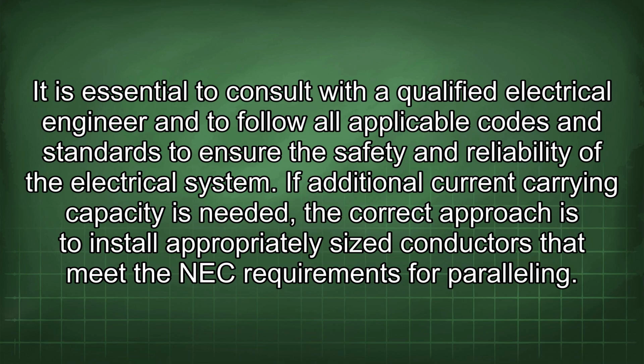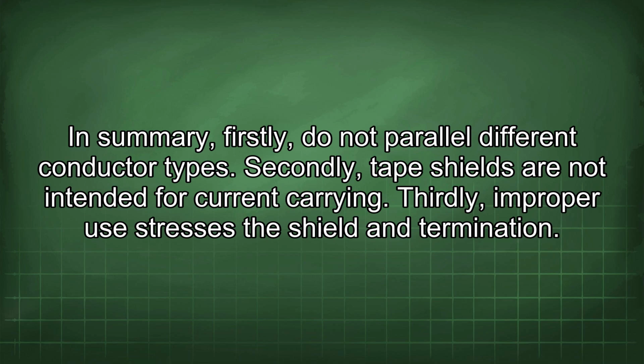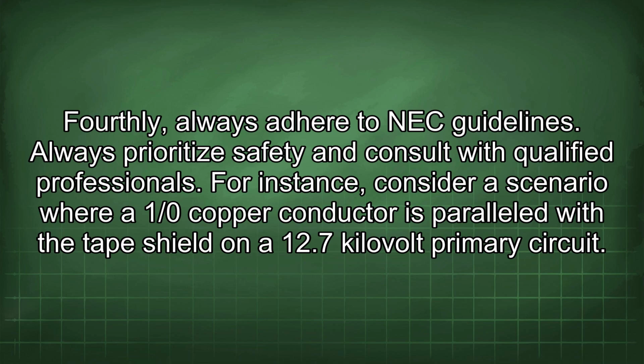If additional current carrying capacity is needed, the correct approach is to install appropriately sized conductors that meet the NEC requirements for paralleling. In summary, firstly, do not parallel different conductor types. Secondly, tape shields are not intended for current carrying. Thirdly, improper use stresses the shield and termination. Fourthly, always adhere to NEC guidelines. Always prioritize safety and consult with qualified professionals.